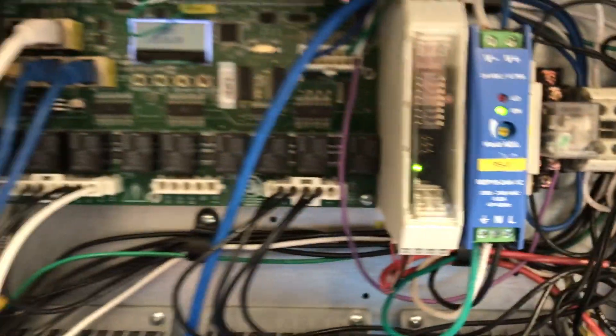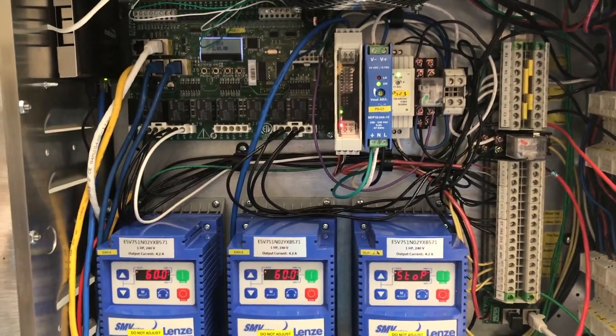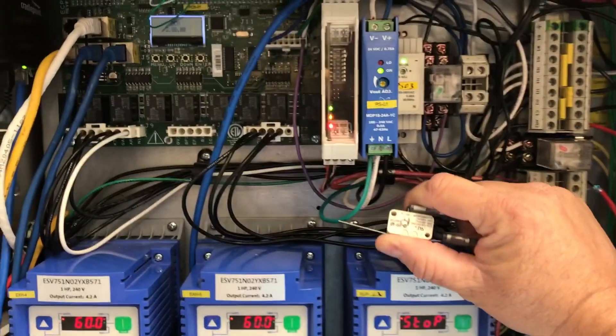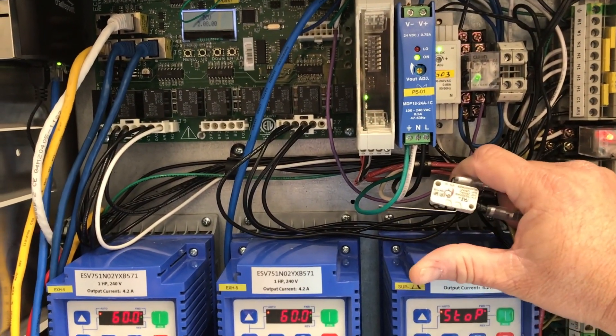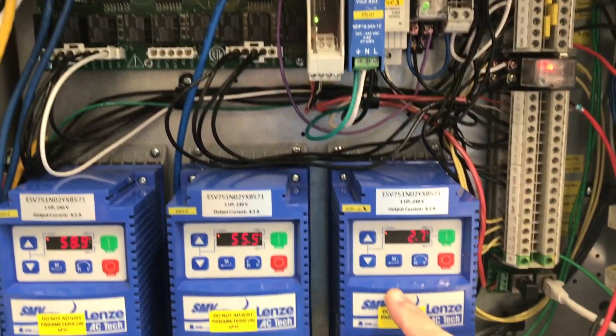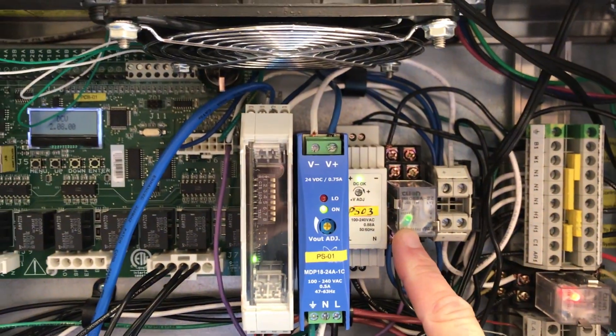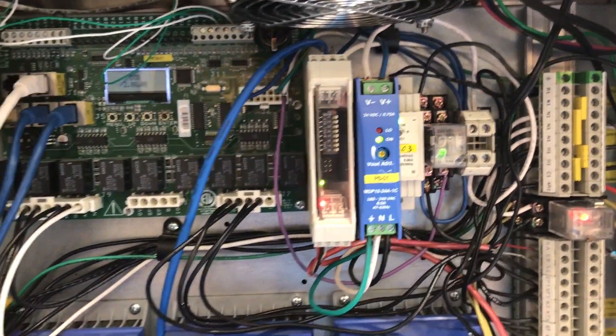The control package will also energize the ST terminal with 120 volts to trip your shunt trip breakers. And if there's an electric gas solenoid, that will be de-energized. Once the Ansul system is reset, the microswitch will go back to its normal position closing C1 and AR1, and the control package will go back to its normal operating condition.